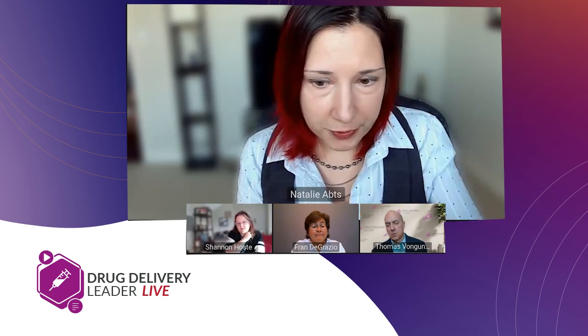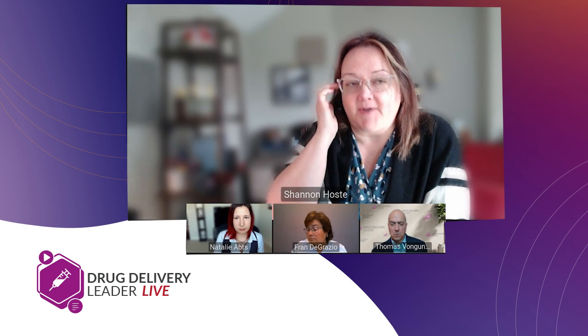No, Natalie, I agree. And I think the thing to remember is when we talk about risk and human factors, there are two purposes for this tool that we're trying to satisfy. For risk, we're trying to estimate and understand the potential risk of our product so we can ultimately mitigate that risk and do a benefit-risk analysis. For human factors, we want to identify any tasks that could lead to harm due to a use error, and then use that to drive the scope of our activities. So in the human factors world, the tool is really there to drive what we need to look at.